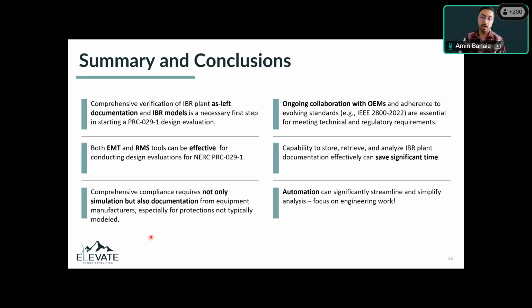So just to summarize, these are some highlights and the important steps that need to be taken when doing a PRC-29 analysis. First one is to verify the as-left settings with the different parameters in PSSE, PSLF, PSCAD, and EMTP models of the plant to make sure that you have good trust in that model. The second one is that both EMT and RMS tools can be effective for doing PRC-29 analysis. And also, do not just rely on your simulation results. Make sure to check those with any documents that you find about the plant and the OEMs as well.